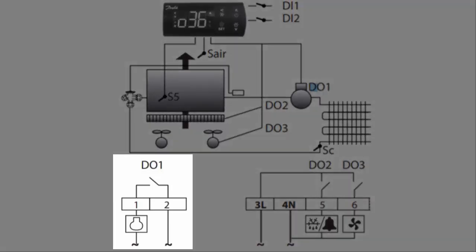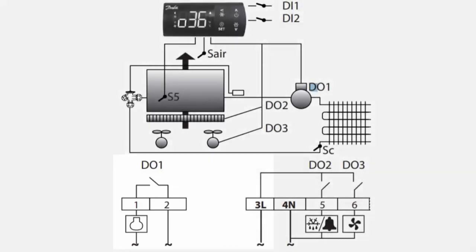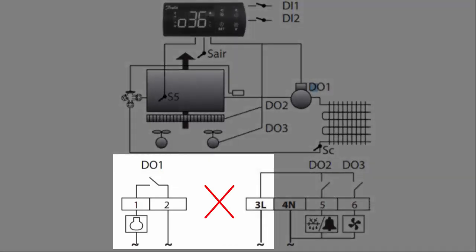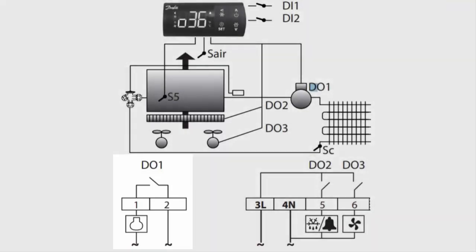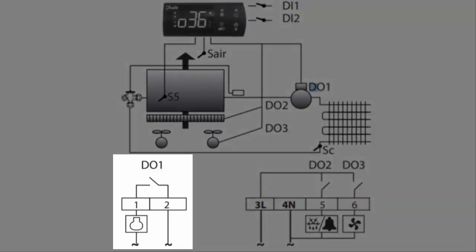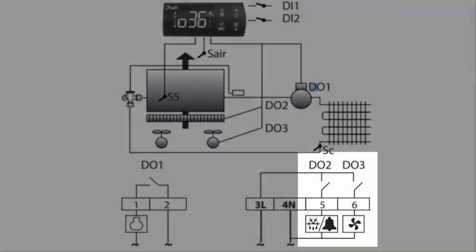DO1 terminals one and two are dry because they don't have voltage intrinsically applied within the controller itself. You have to connect to either terminal one or two with a constant power supply and feed it through to the device. To simplify: DO1 is dry, DO2 and DO3 are wet.